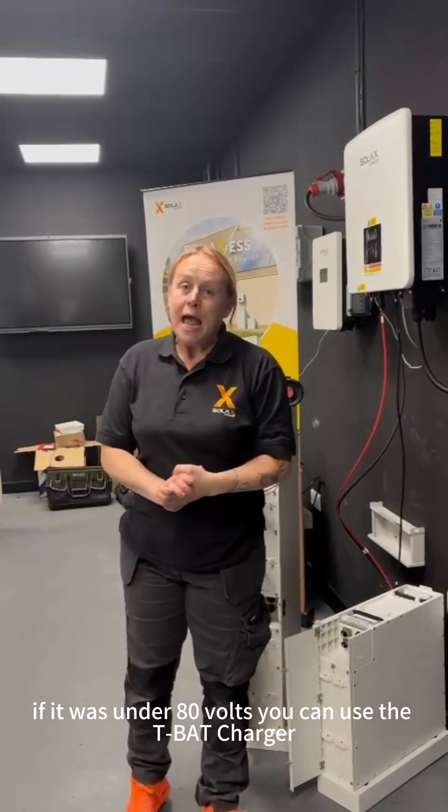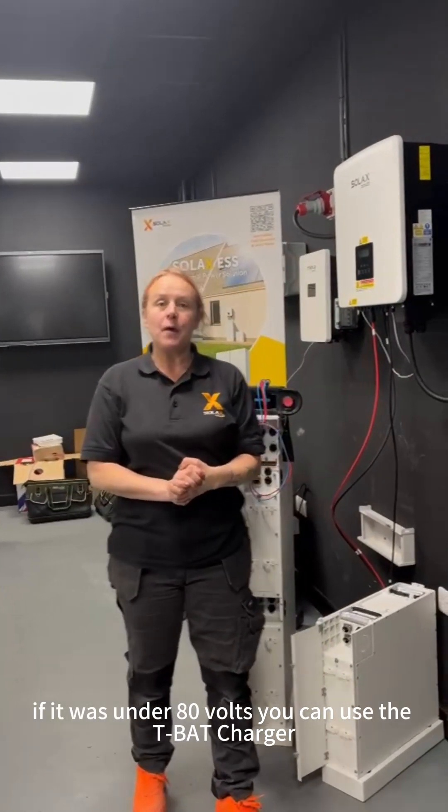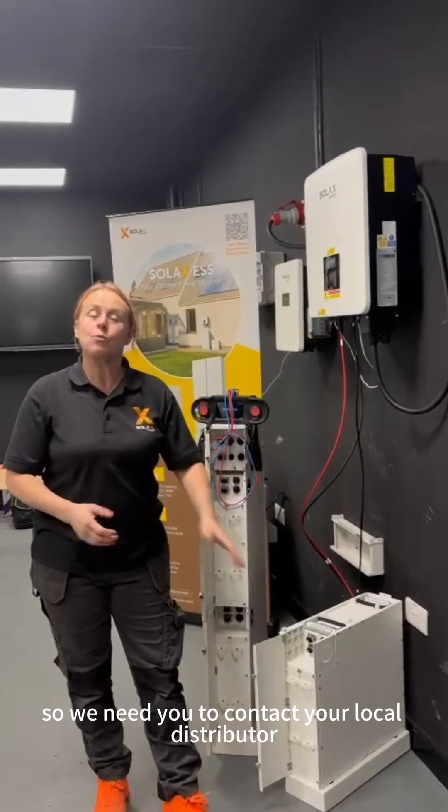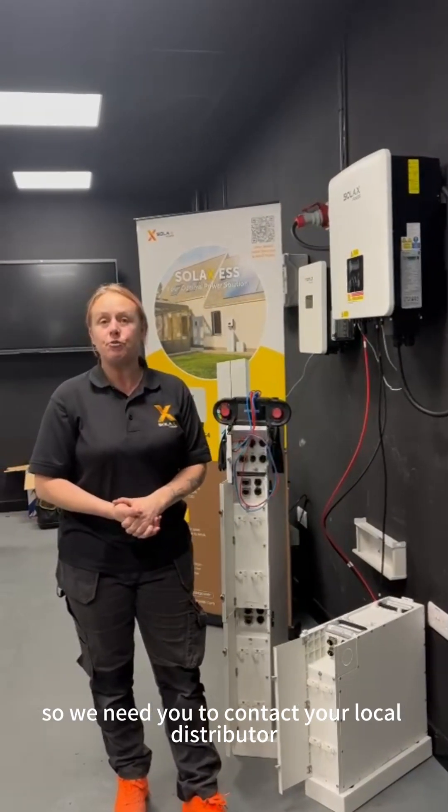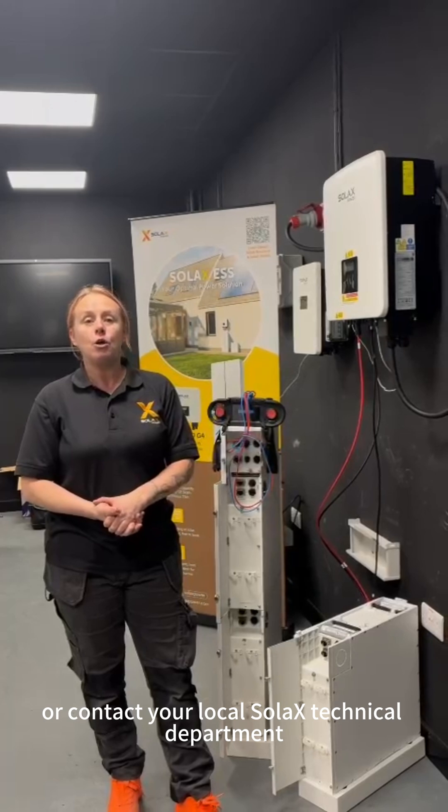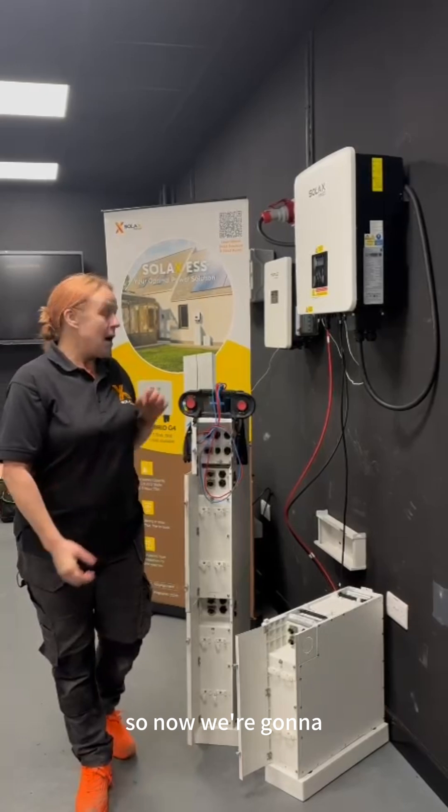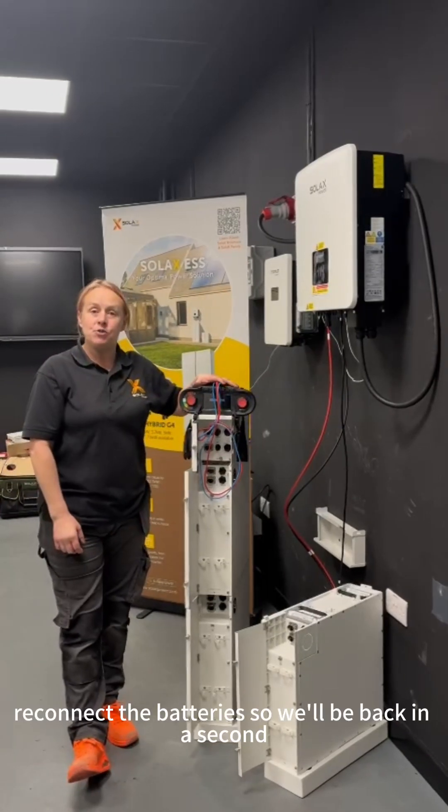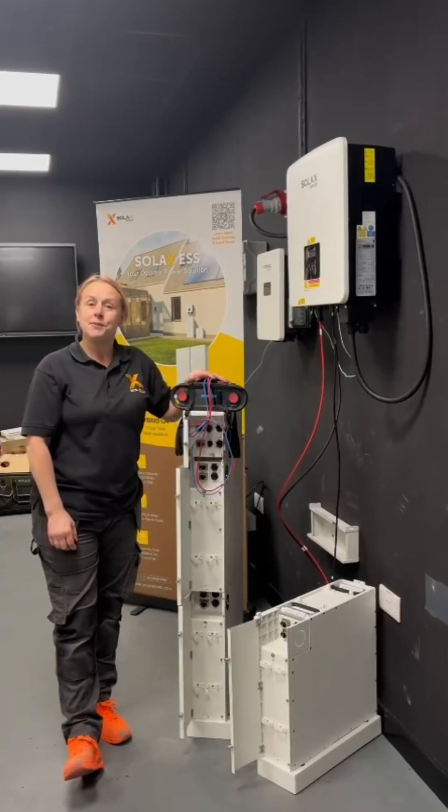Because we have zero volts DC, we know that this third battery is faulty. If it was under 80 volts, you can use the T-BAT Charger. However, we've got zero volts, so we need you to contact your local distributor or contact your local Solax technical department, who will offer you further assistance. So now we're going to reconnect the batteries.